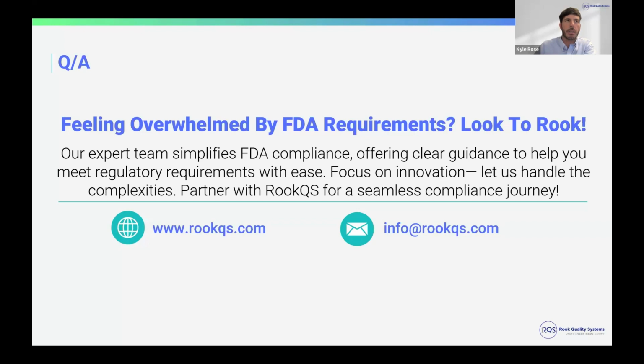I've also seen similar questions of, this is a draft guidance, do we need to comply with it now? Even though it's not finalized, you should still use the draft guidance and align your testing with it if you are in the process of developing a device now or getting ready to do testing, biocompatibility, or chemical analysis. The draft guidance is draft, but it is published. So they went through that step of publishing it, but it's still draft. But you should still use that information with your testing and identification of your testing.